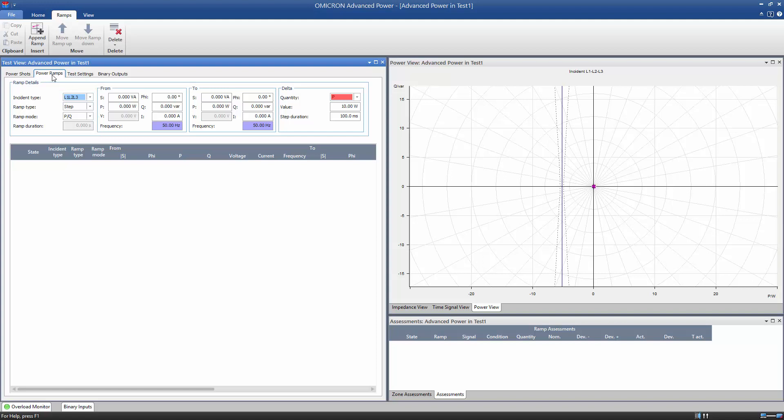We define the beginning and end of the ramp in the From and To sections. We start from 80% until 120% of the expected pickup value. Don't forget to set the angle phi to 180 degrees to simulate the reverse direction of power.